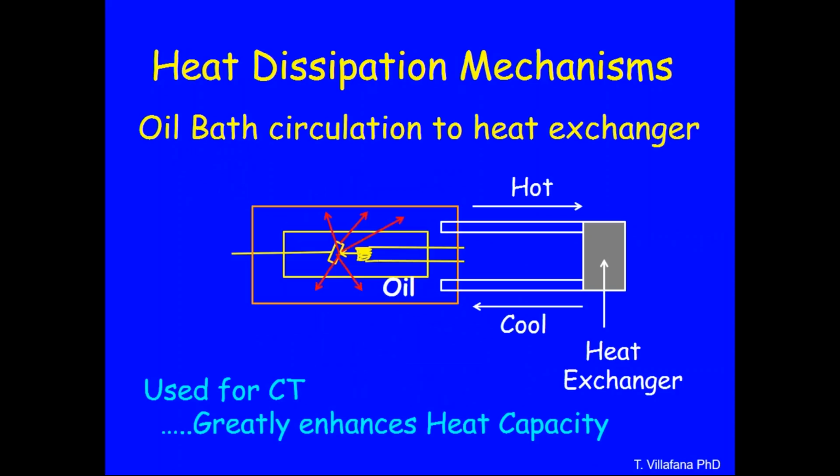Do realize that CT scanners are the one modality that produces the greatest amount of heat. Remember that in CT scanning, you're spiraling around the patient, so you have relatively long exposure times, and all CT scanning is done at very high voltages. The very highest voltages that are used in radiology are in CT scanning. So in general, the heat loads are very, very high, the highest in all of radiology.